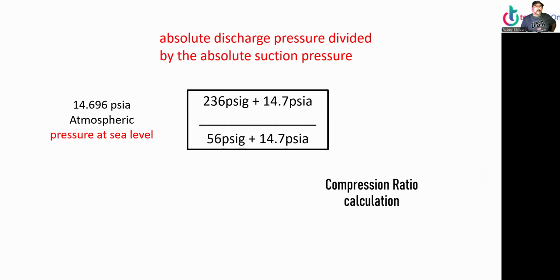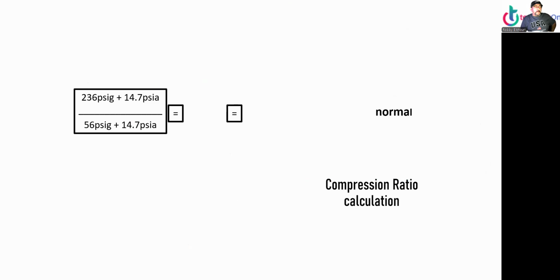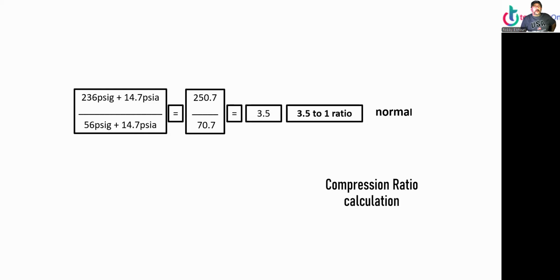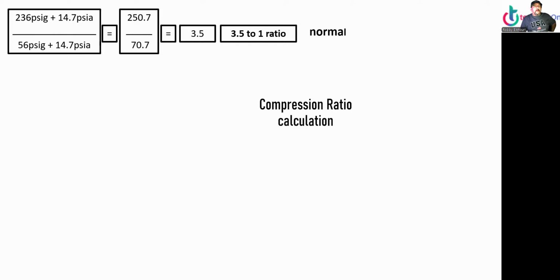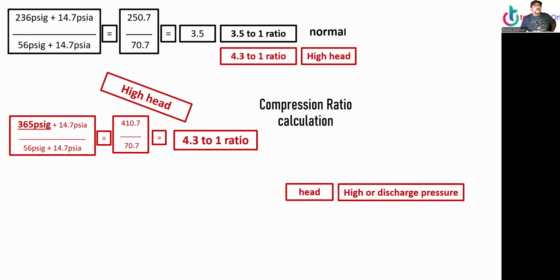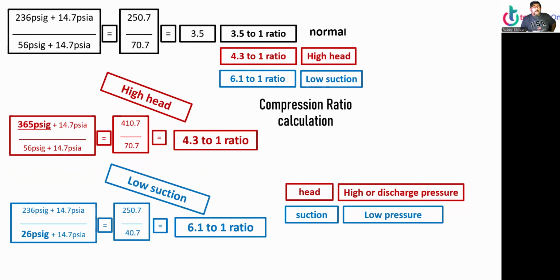First, absolute discharge pressure divided by absolute suction pressure. You have to add the atmospheric pressure. Atmospheric pressure at sea level is 14.696. So, calculations: discharge pressure divided by suction pressure, and you add the 14.7. Math gives 3.5 compression ratio, 3.1. 3.1 to 5, that's your ratio, this is normal. Now, if we have high head pressure, and head pressure also means discharge pressure, then what's going to happen to the compression ratio? 4.1, 4.3 to 1. And if we have low suction pressure, also a 6.1 to 1 compression ratio.